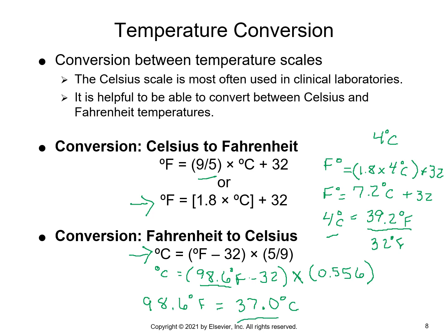And if you're in the blood bank world, 37 degrees is the temperature that we have the fresh frozen plasma thawers at. So the water baths are set at 37 degrees Celsius for thawing fresh frozen plasma. So that is about body temperature. So anytime I go to do that, I make sure that it says it's about 37 degrees.